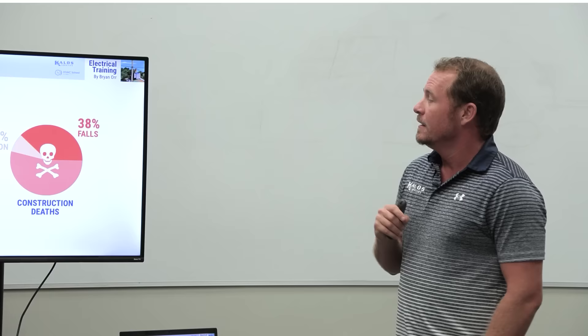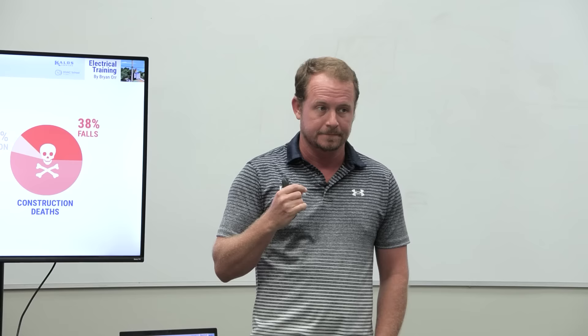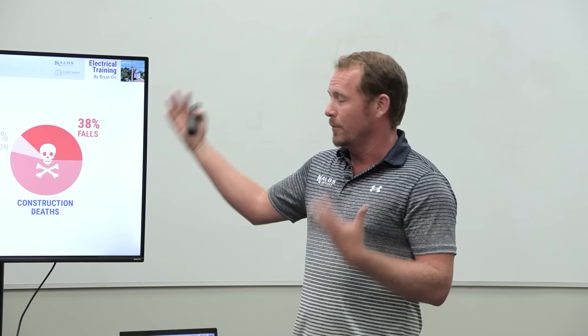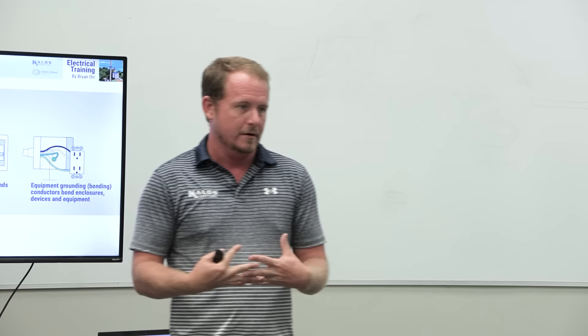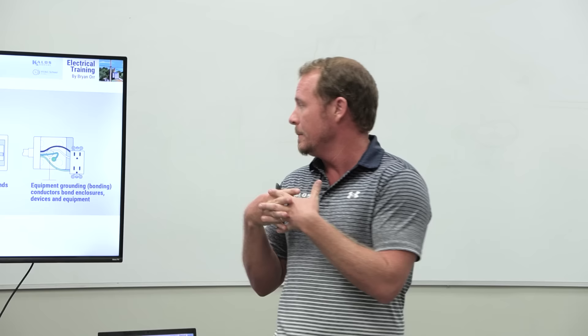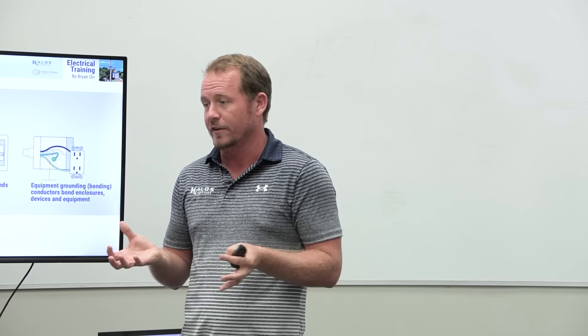Fall risks: a huge portion of deaths associated with electrical work are related to falls—much greater than direct electrocution. You get shocked and you fall back. So ladder safety and proper harnessing become really important when working on any electrical. Grounding and bonding: we need to connect all the metal electrical parts together when working in an electrical system. One reason for this, especially with pool equipment or salty environments, is to actually prevent corrosion—bonding things together prevents galvanic reactions that cause rust.